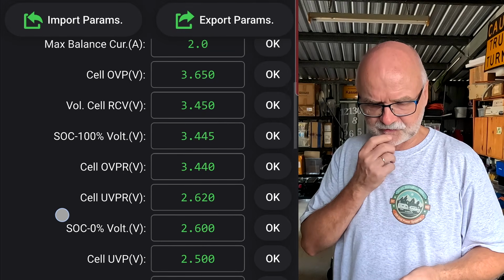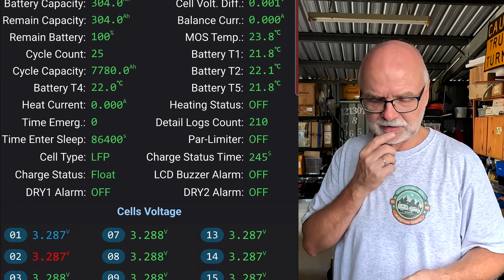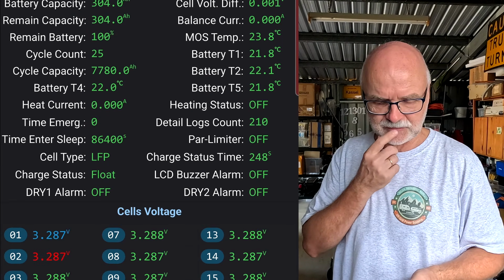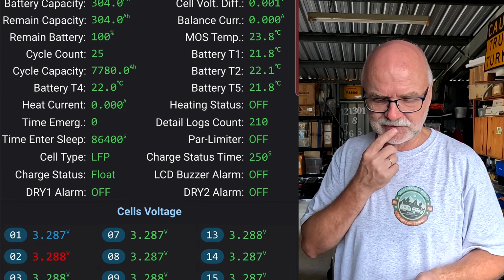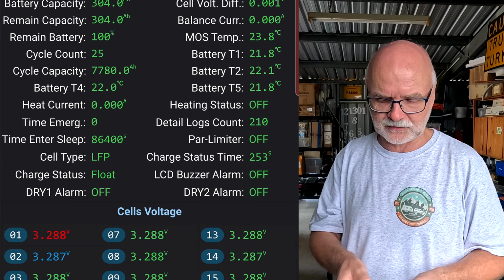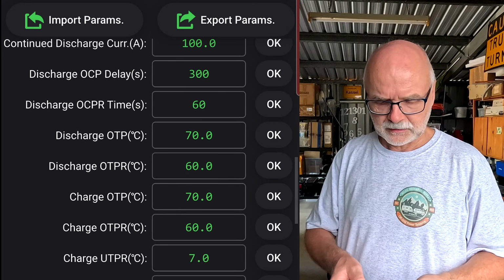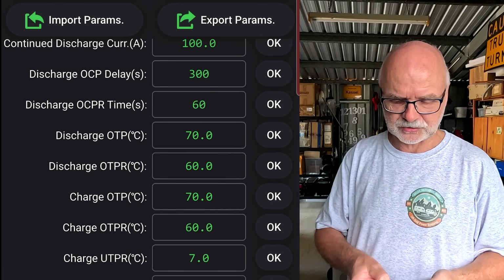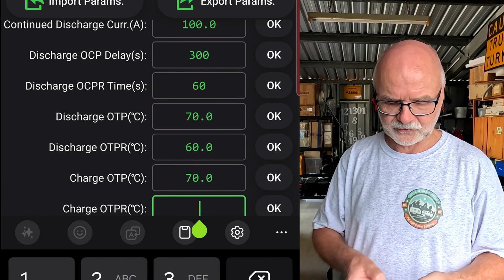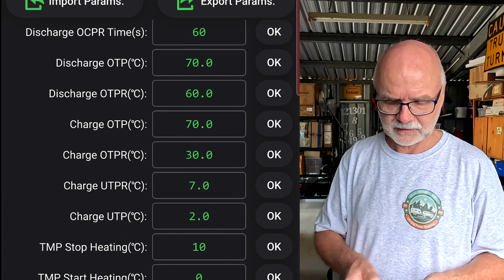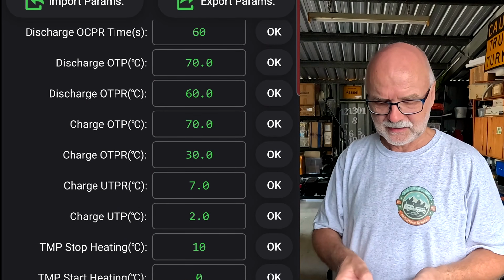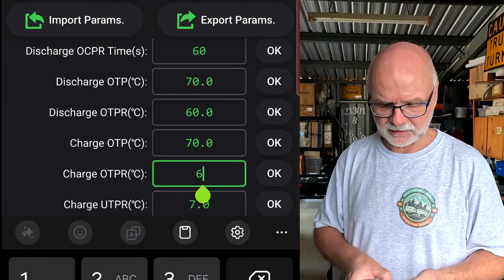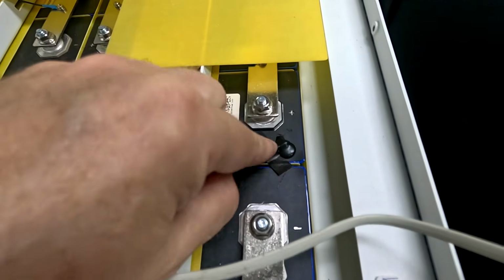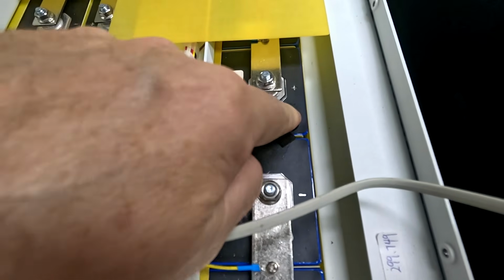Okay, let me see if I can trigger an over voltage, an over temperature situation here with one of the batteries. But I don't think I'm able to, because the maximum is 22.1 in this battery. Charge over temperature protection, the recovery. We set this one to 20, but I don't think... No, the lowest is 30 we can set. Okay, let's try something else. They have used silicon glue here to put the temperature sensors on top of the cell, so I cannot really heat them up. Ah, hang on.